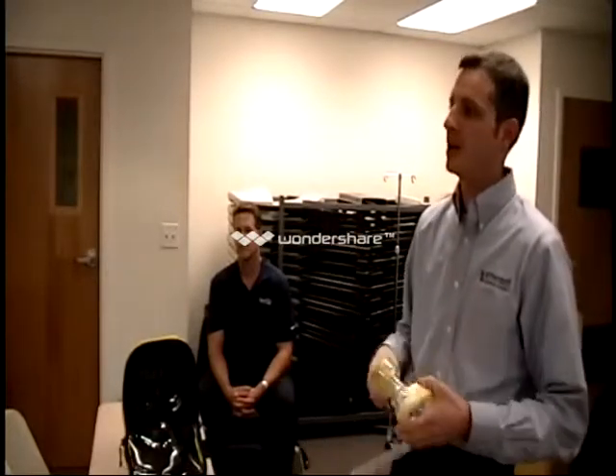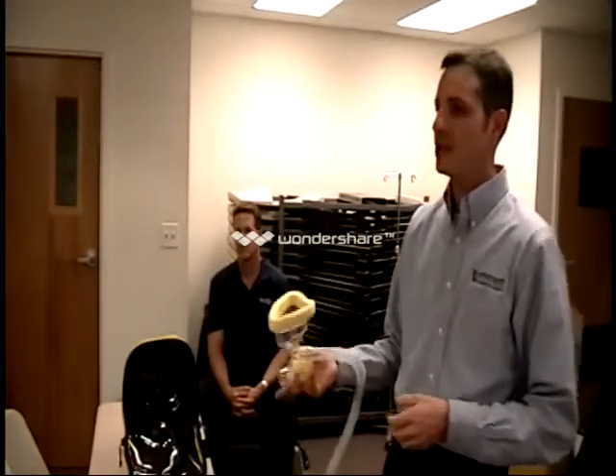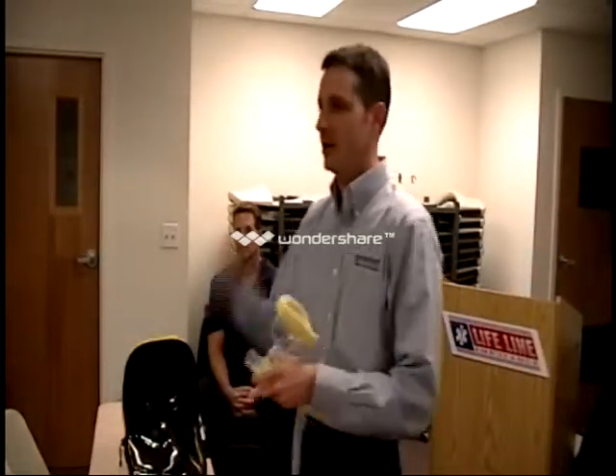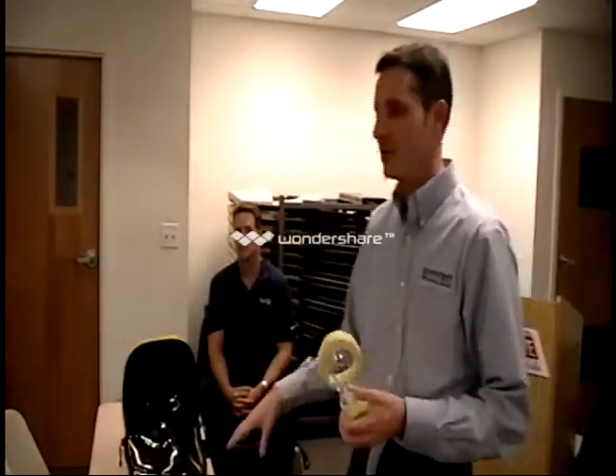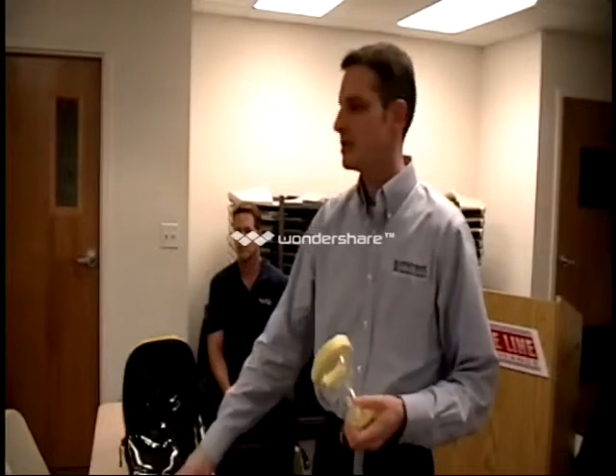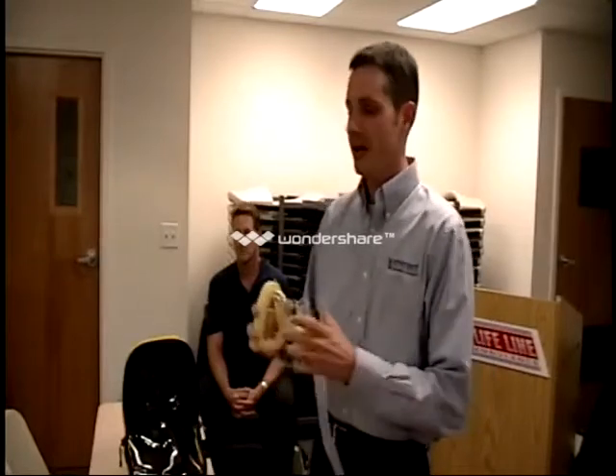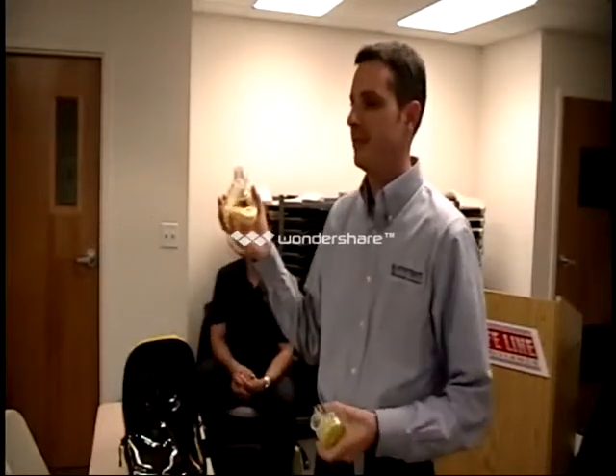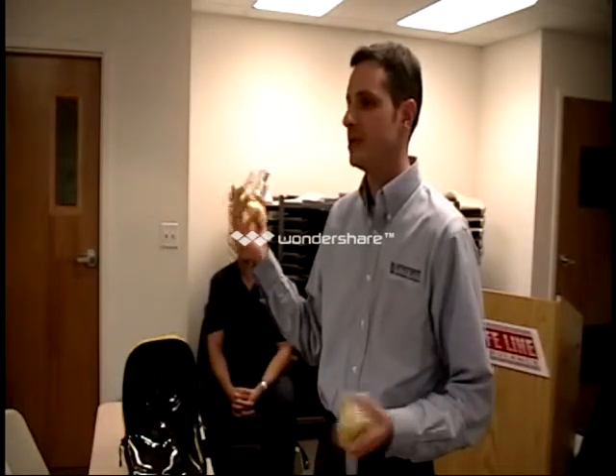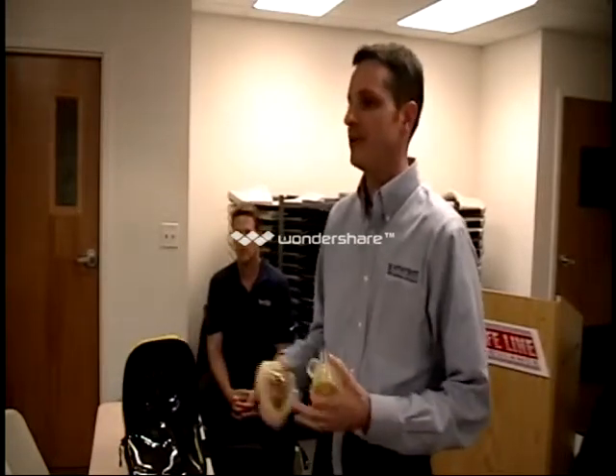You should only hear inhalation and exhalation. There's no backup ventilation on this device, so if the patient stops breathing, you've got to discontinue use. They won't asphyxiate on the system if you run out of oxygen because there's an anti-asphyxiation built in. But if you do run out of oxygen, you might as well just use the mask and bag them, because you're not going to be able to do any other benefit with the system on at that point.